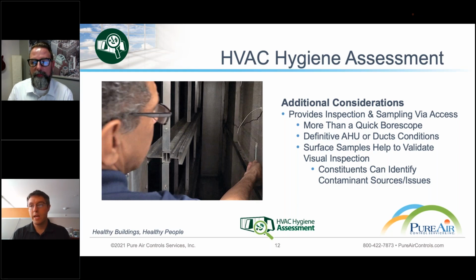That's indicative of standing water in the right conditions. It's dark, it's damp, microbials love that. The water stands there, or there's a constant source keeping that pan at a certain level, and contaminants build up. Dust comes into the system and interacts with that water, so it keeps getting a food source. Some bacteria can even eat into the iron, utilizing it as a food source, as we see with corrosion.